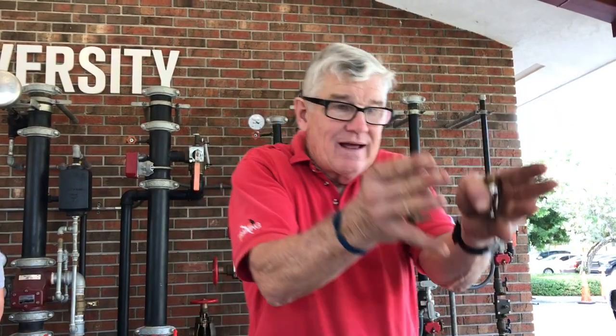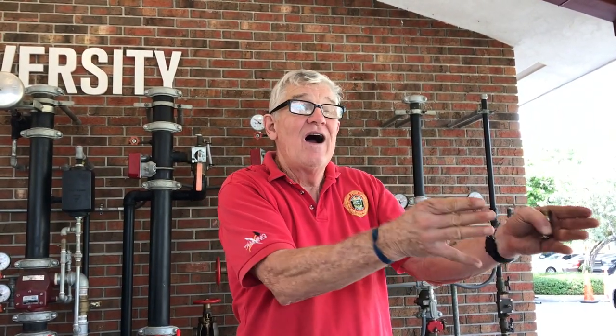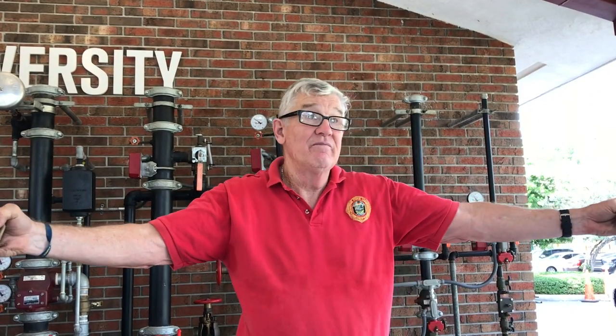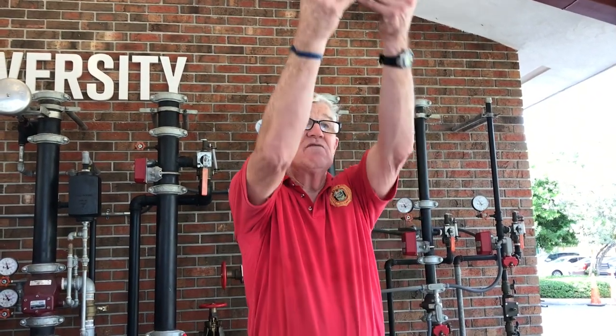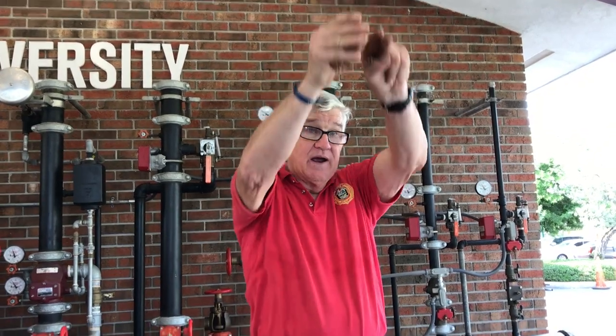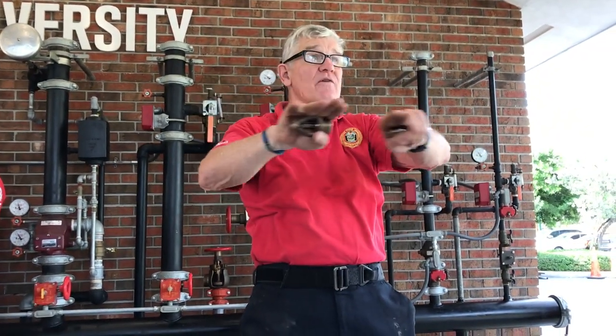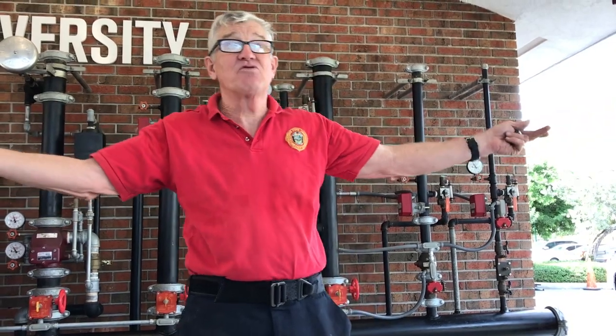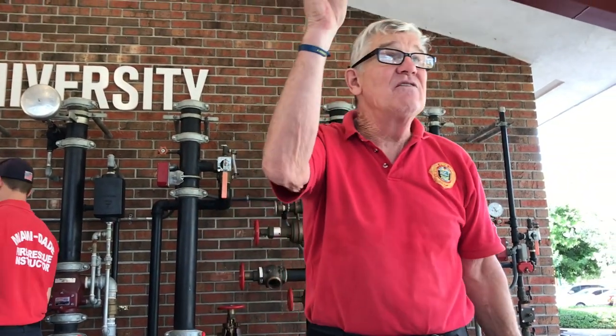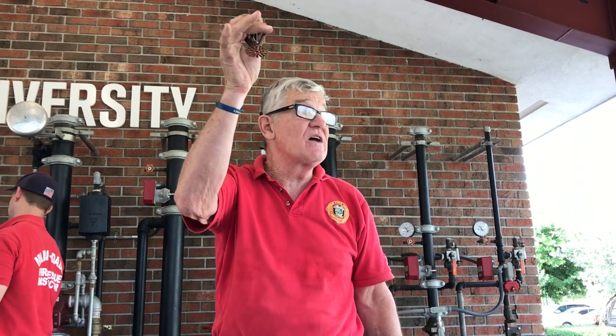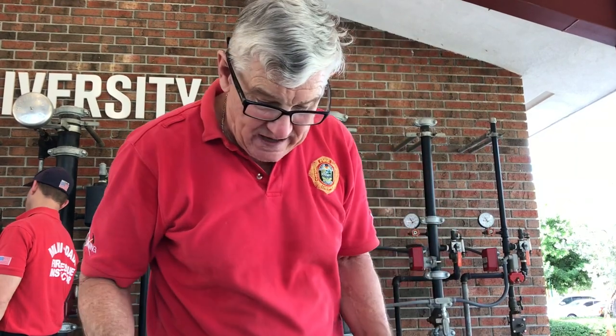He assumes the liability. And the way they get away without having sprinklers in the racks at IKEA and similar occupancies is the slats are just slats, they're not solid shells. Hence, the heat can convect up, water can cascade down. If you have solid shells, you're gonna have to have sprinklers in the rack. This guy can flow as much as 175 gallons a minute. That's how they get away without sprinklers in the racks at IKEA furniture.